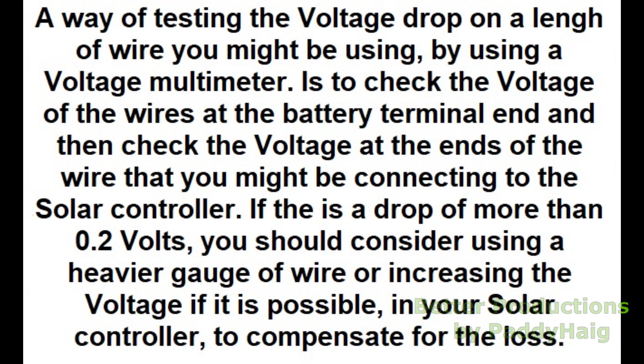If not, your cable wire is too thin. If it's a very small amount of voltage drop, you might compensate by programming a slightly higher voltage into your solar controller, if possible. But it's probably best just to get a heavier gauge of wire.